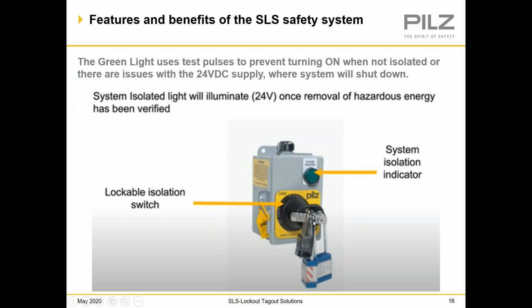And so basically, all you do is obviously turn the switch to the lockout state and lock it and wait for the green light to come on. Now, the green light is going to come on, but it's not going to come on immediately because there might be other things going on within the machine or the cell that have to dissipate other kinds of energy within the cell that are initiated by electrical power, which you're turning off here.